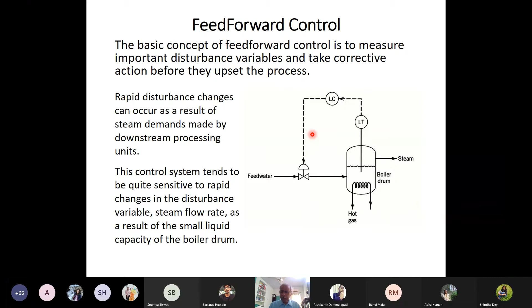Okay, so let us now go to the feed-forward control. In the case of a feed-forward control, what we can do is, instead of measuring the level, we measure the disturbance. So we measure the steam flow rate, and as the steam flow rate changes, we also change the feed water. In this case, theoretically, this will give you a perfect control of the level, because immediately when the steam changes, we take a corrective action.